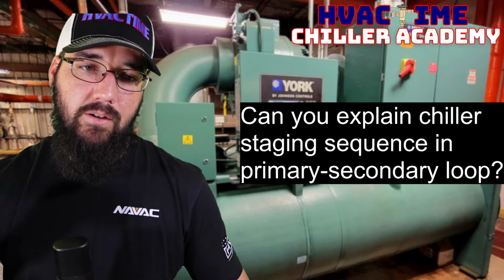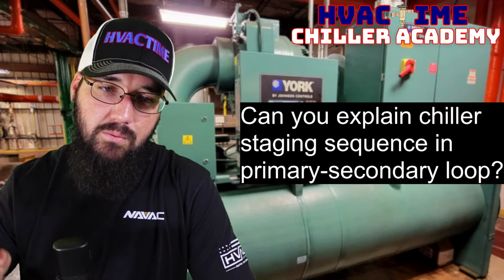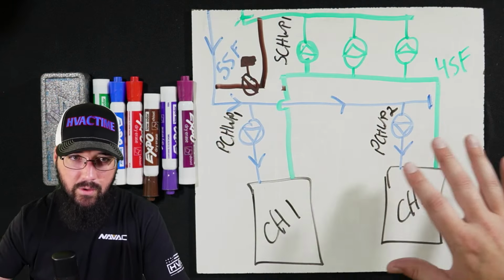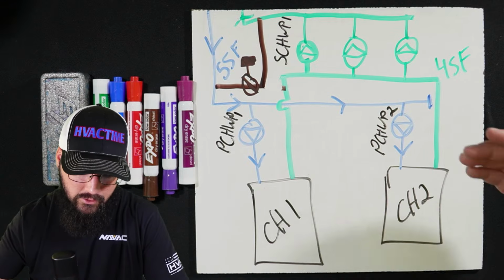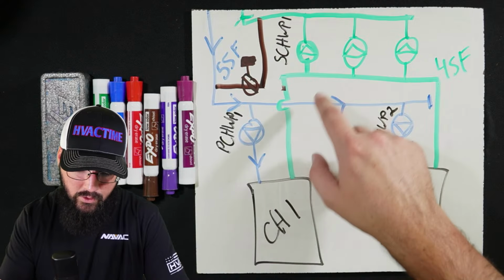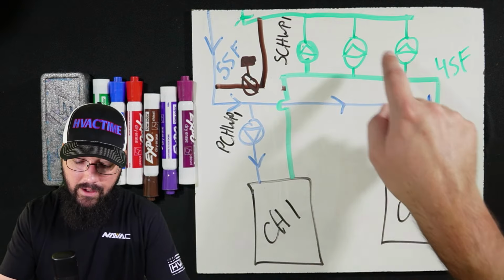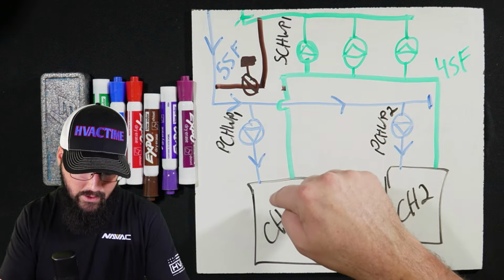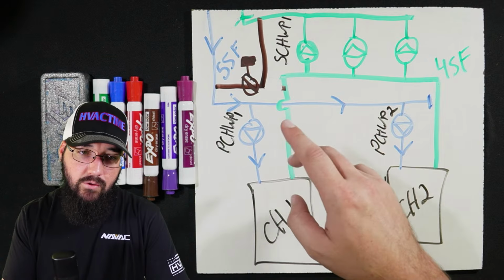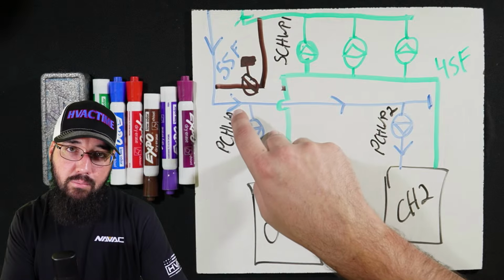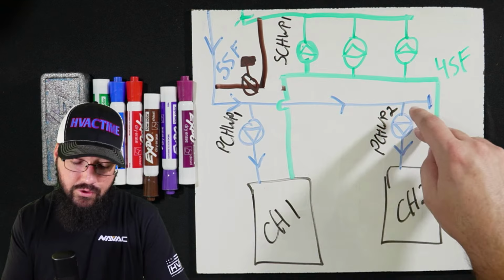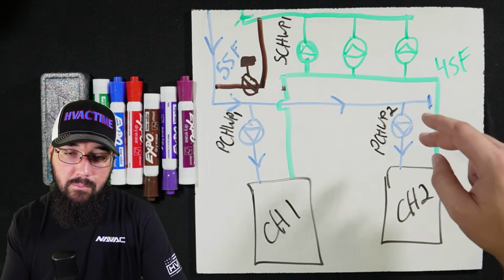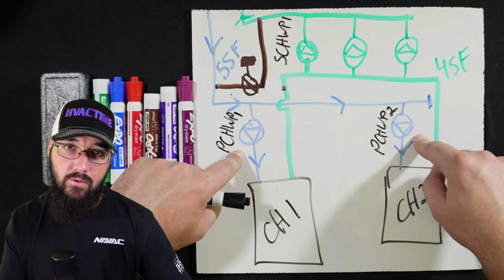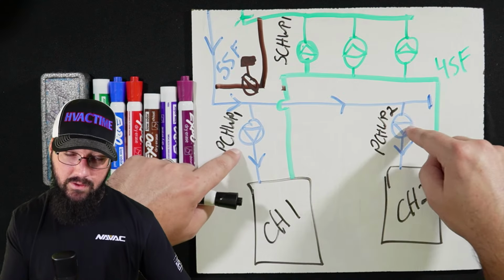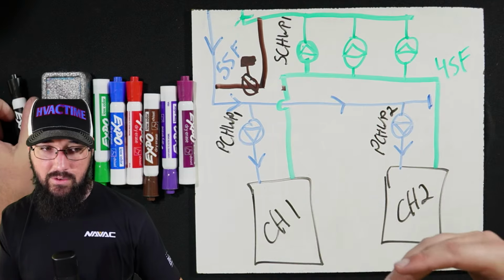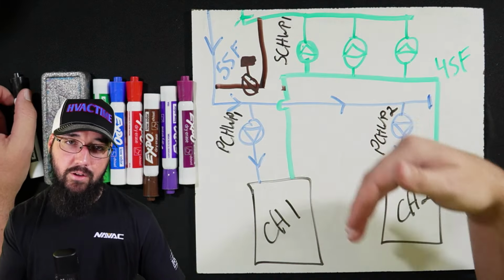So just to recap on the question, from a staging sequence perspective on the primary secondary loop, this is what a primary secondary loop will look like, and that is our main staging. If we want to bring on chiller 1 or 2, these don't really affect what the secondary pumps need to do. They only affect which primary pump we're going to run. So if we wanted to switch over to chiller 1, we're going to bring on primary 1 for that chiller, and we could shut off chiller 2 and primary pump 2. Now keep in mind, the chiller is going to shut off before the pumps. So we shut the chiller off. These pumps need to stay on for several minutes to let everything in the chiller balance out, stabilize, do what it needs to do. And then we can shut the pump off.